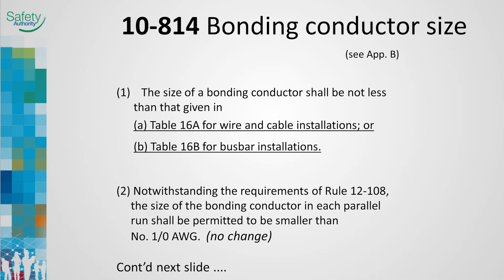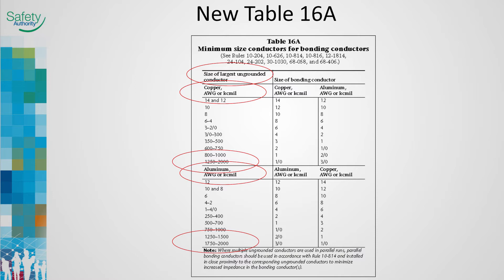Rule 10-814, bonding conductor size, sub-rule 3, provides direction for selecting bonding conductors when circuit conductors are paralleled. The sub-rule has been edited to separate the two types of installation methods. Bonding conductors selected using Table 16A are based on circuit conductor size, whereas bonding conductors selected using Table 16B are based on the ampacity of the bus bar installation. New Table 16A now specifies the size of the largest ungrounded conductor. The table has been separated to provide separate copper and aluminum wire references. The bonding conductor sizes have been slightly revised to correct for ampacity adjustments to some conductors. The size of the ungrounded conductor is now capped at 2000 kcm.